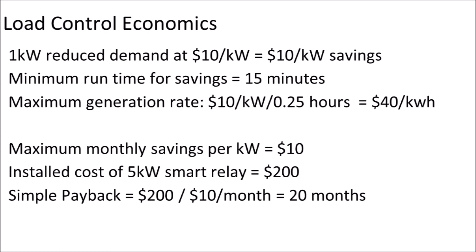Commercial customers have the greatest opportunity for savings through load control. Once commercial building energy exceeds 200 amps — the maximum of a standard residential electric service panel — the business incurs electric demand charges. Demand charges are calculated at the highest 15-minute peak period of electric use for the entire month. Even with a modest demand charge of $10 per kilowatt during that one 15-minute period, the electricity is costing the building owner $40 per kilowatt-hour for each kilowatt of peak demand.